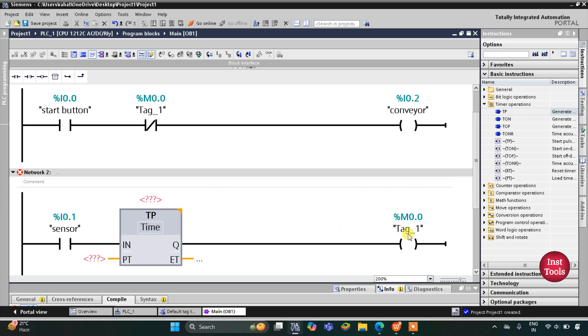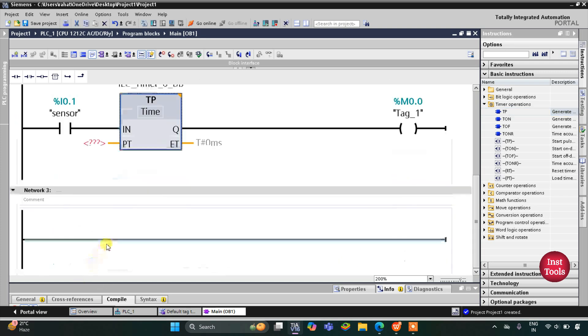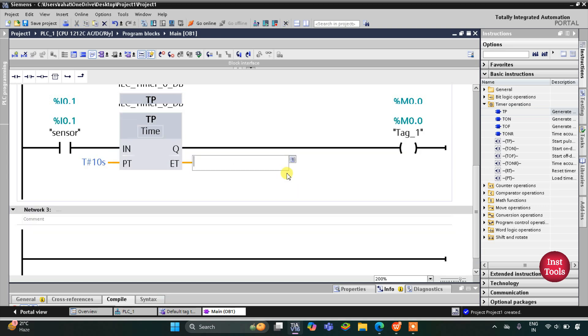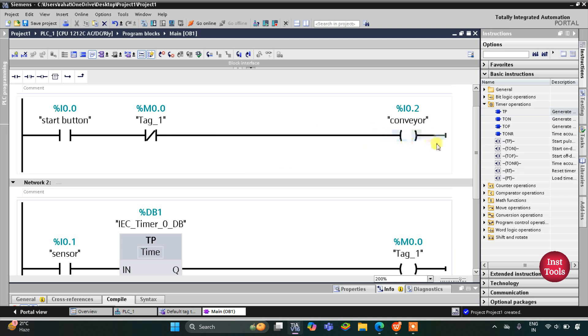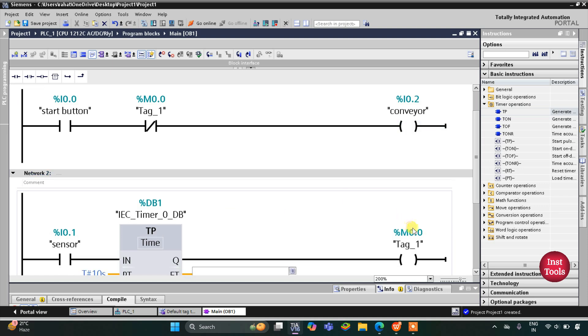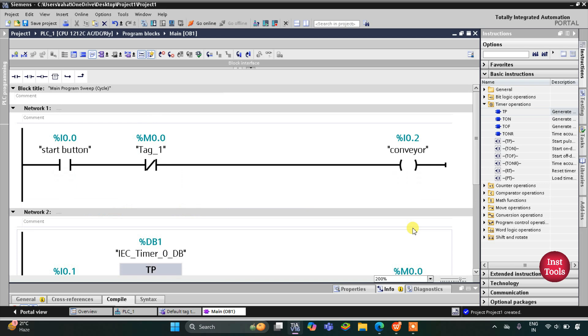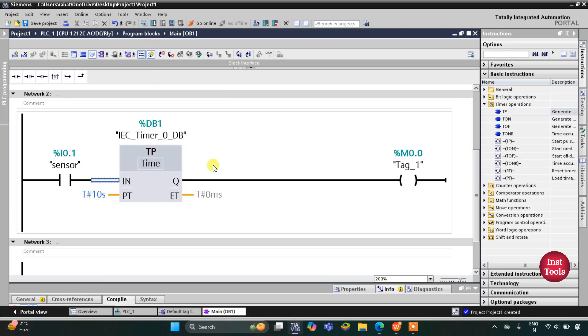M0.0 should remain on for only 10 seconds. So this conveyor will turn off for 10 seconds, and after 10 seconds M0.0 turns off. When M0.0 turns off, the conveyor will once again start. When the conveyor gets stopped, the puncher will be activated.